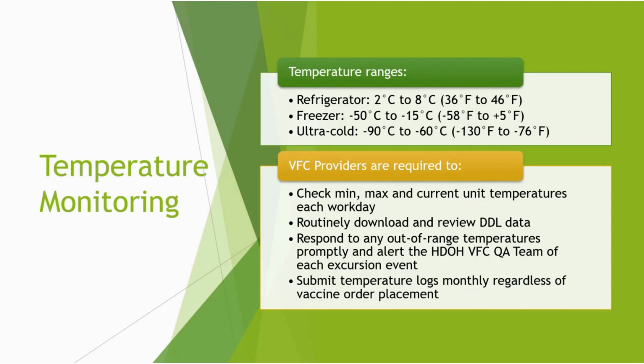Monitoring vaccine storage equipment and temperatures are your daily responsibilities to ensure the viability of your vaccine supply and the safety of your patients. Implementing routine monitoring procedures can help you identify temperature excursions quickly and take immediate action to correct them, which will prevent vaccine loss and the potential need to revaccinate patients. Here you'll see the temperature ranges for each unit. The refrigerator should remain between 2 to 8 degrees Celsius, 36 to 46 degrees Fahrenheit. The freezer should be between negative 50 degrees Celsius to negative 15 degrees Celsius, with the corresponding negative 58 degrees Fahrenheit to positive 5 degrees Fahrenheit.